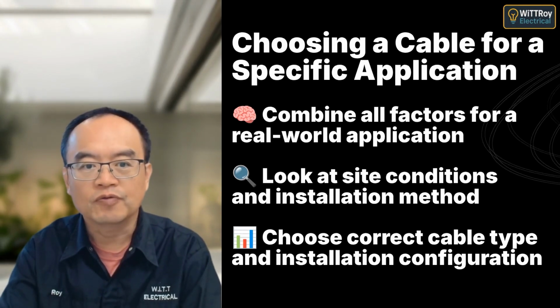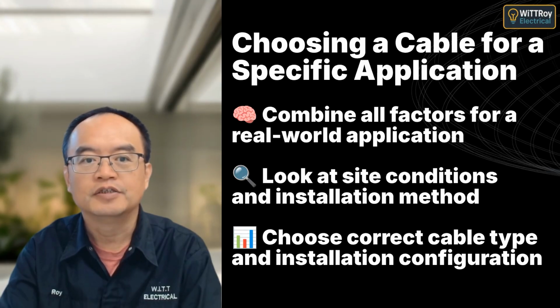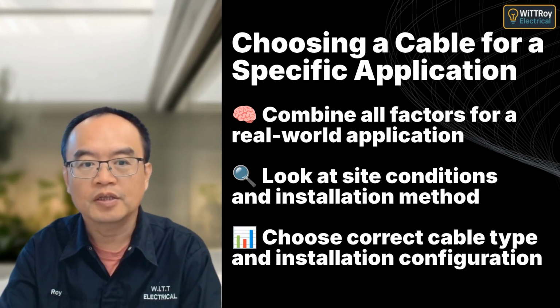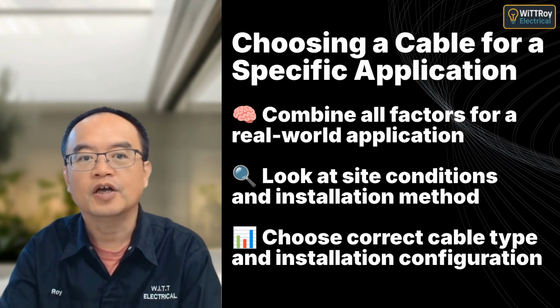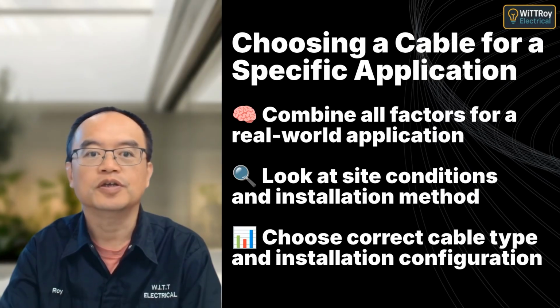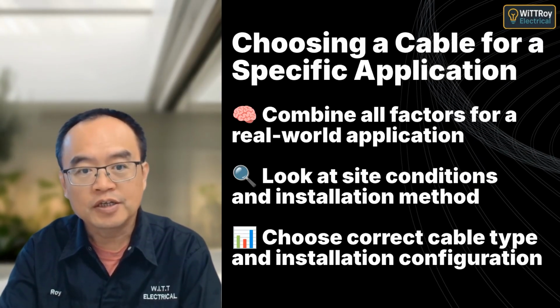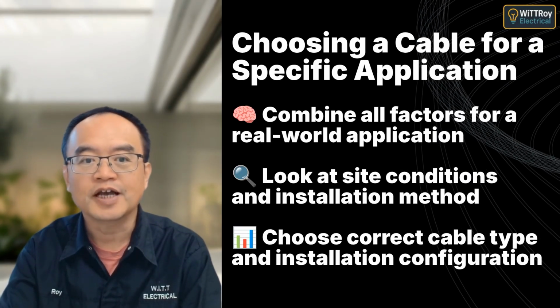To assess a cable for a job, combine all the above factors. For example, a long run in a hot ceiling space may need a larger cable to handle voltage drop and heat derating. Always think about how the actual job site affects the cable's performance.